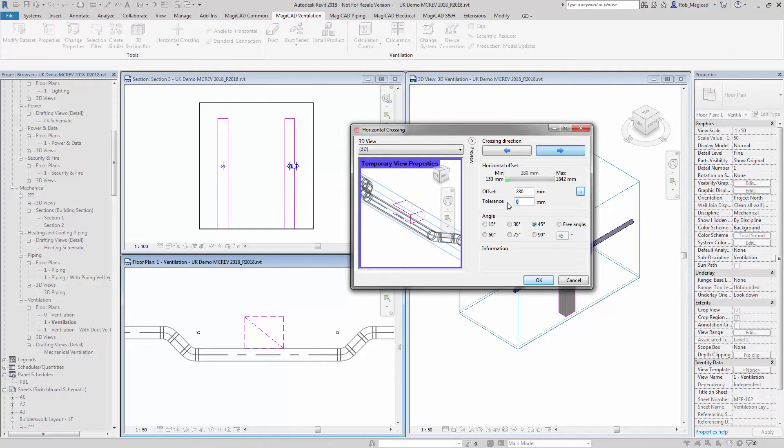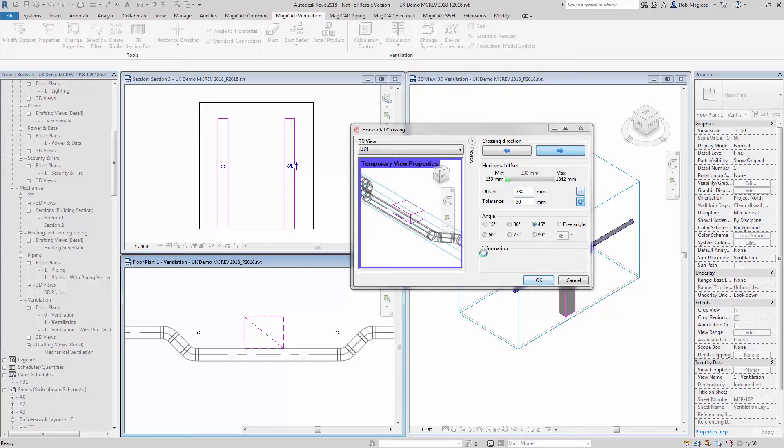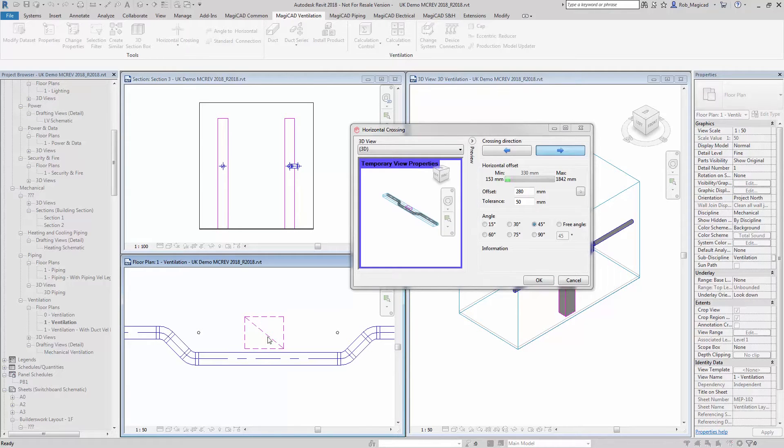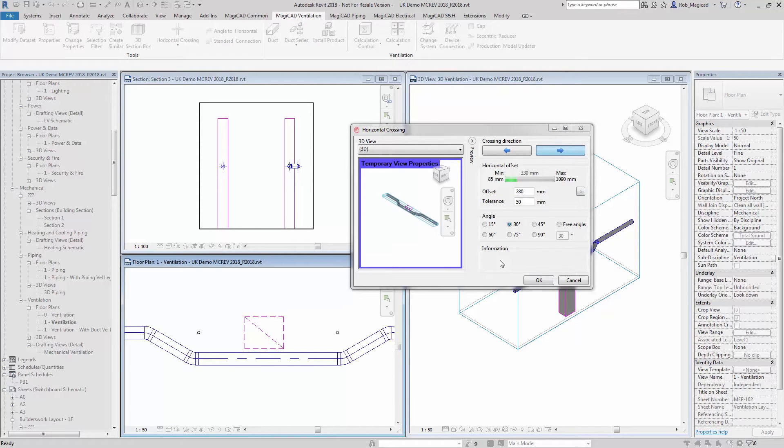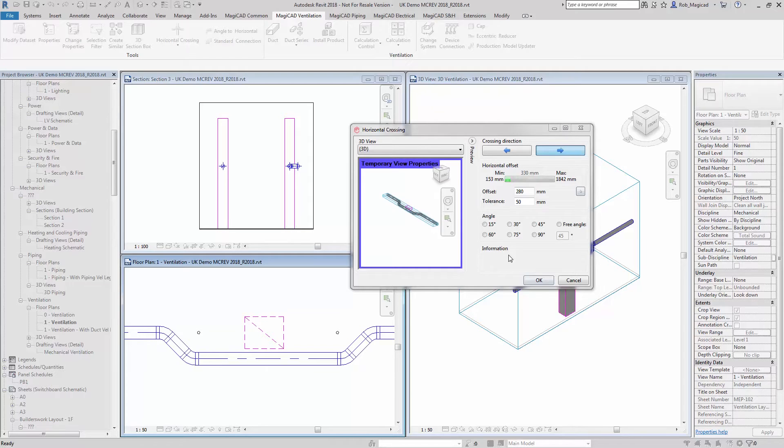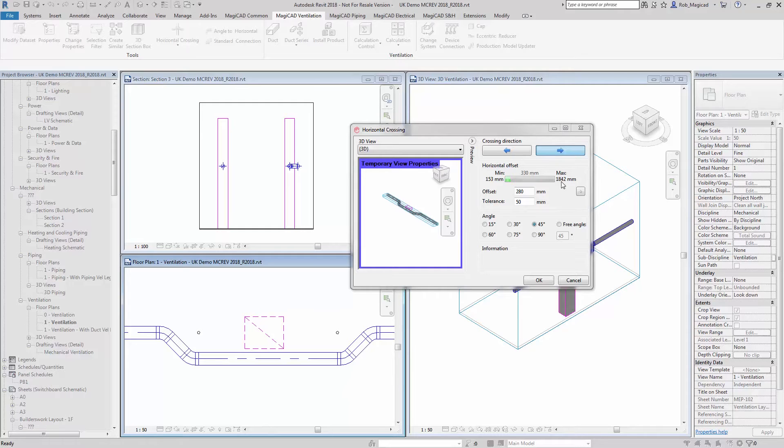We can put our tolerance, so this is a gap between the two objects, in this case ducts, so you can see there a 50mm gap. You can choose the angle, so a shallower or tighter angle as required. It will also give you the maximum offset that is possible with these angles because obviously each duct angle, whether it's steep or shallow, will have a maximum ability before it collides with each other on the fittings in the middle. So in this case, you can see the maximum there.